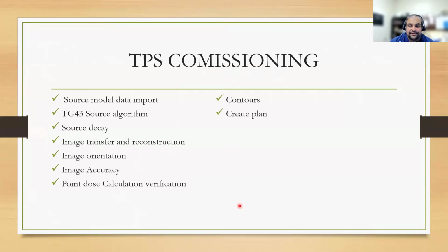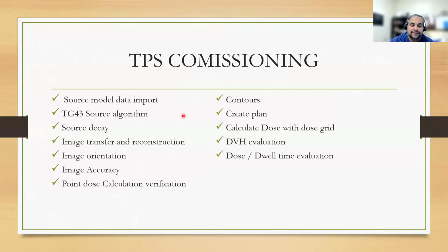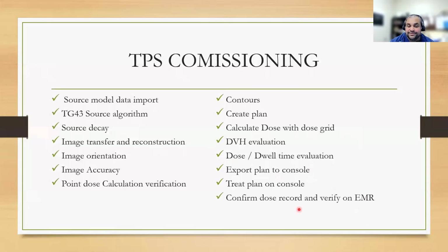So as mentioned, for your TPS commissioning, you have to import your data model, TG43 source algorithm, source decay, and image transfer and reconstruction. There's image orientation, point dose calculation verification, testing your contours, creating a plan, calculating your dose with the dose grid, evaluating your DVH, and dose and dwell time evaluation. Then treatment plan export to the console, treat the plan, and then confirm the dose and record and verify it in the EMR that you use in your clinic.